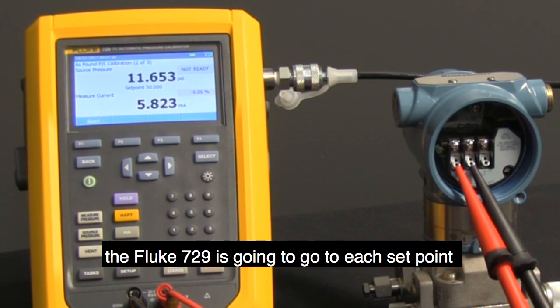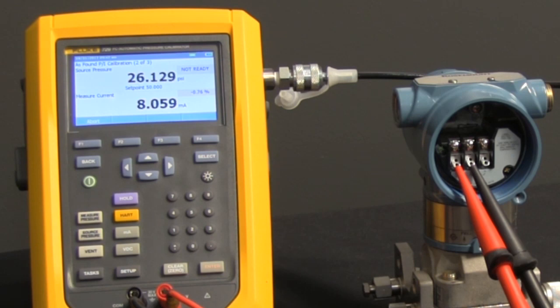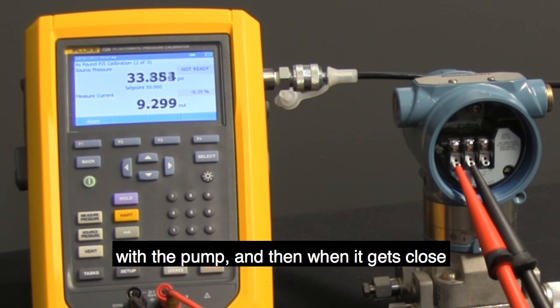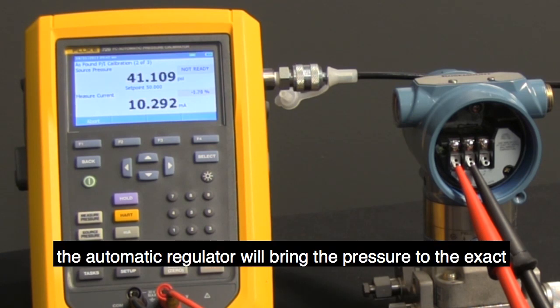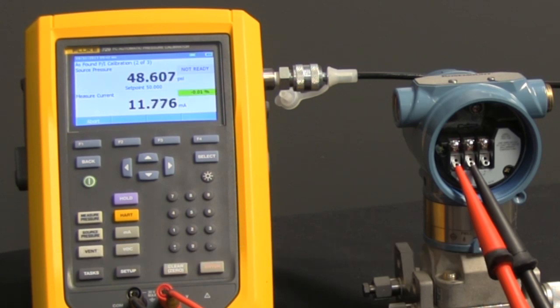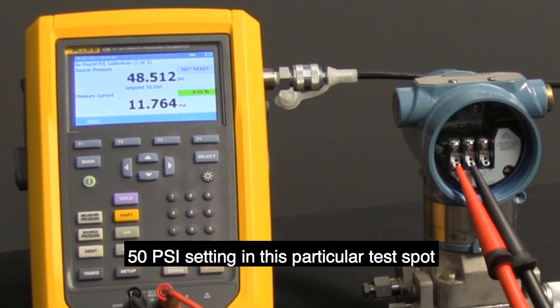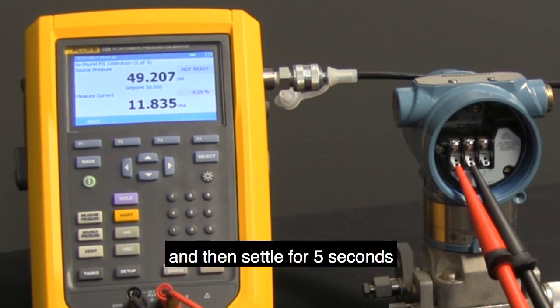The Fluke 729 is going to go to each set point with the pump, and then when it gets close, the automatic regulator will bring the pressure to the exact 50 psi setting in this particular test spot, and then settle for 5 seconds, taking the 4-20 milliamp reading.